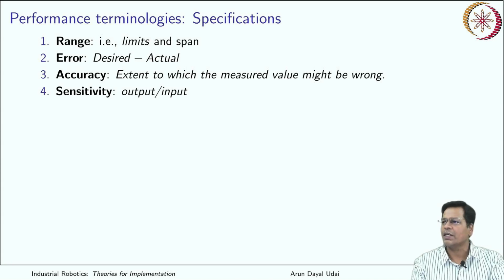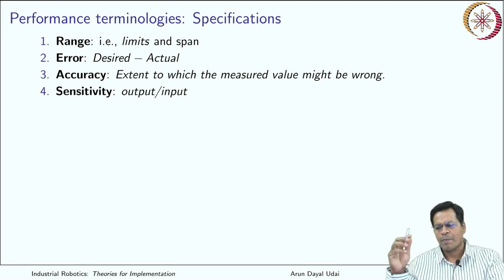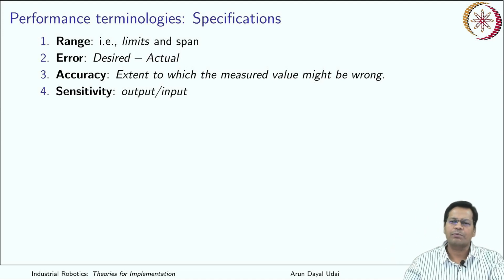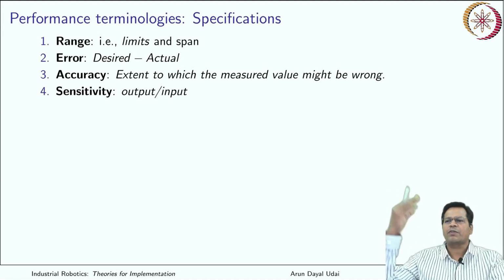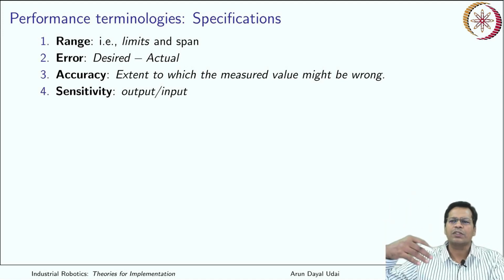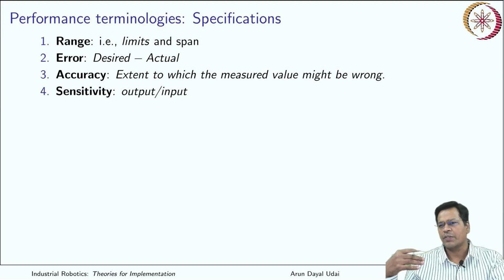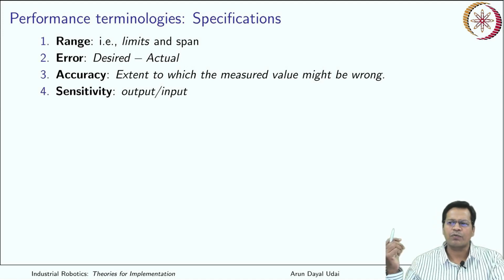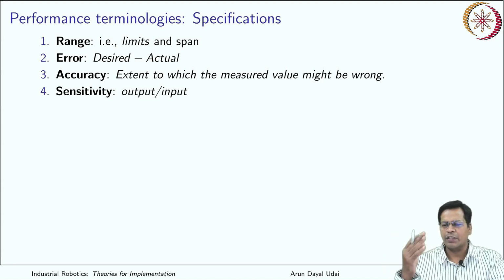And sensitivity - your device sensitivity is not always desirable. If it is oversensitive, it becomes very difficult to measure something. Just like a weighing machine - you put one small weight on top of it, it immediately starts fluctuating, goes very high, overshoots, then comes back. So they may be very sensitive even to a small amount of weight, making it very difficult to see the actual value it should give.